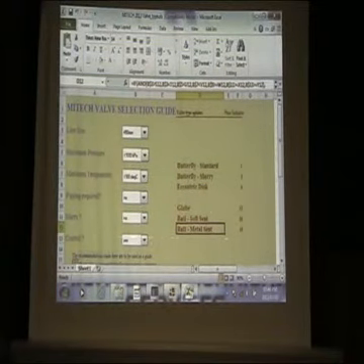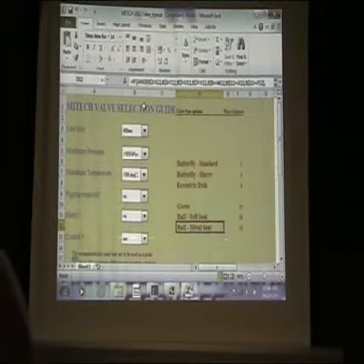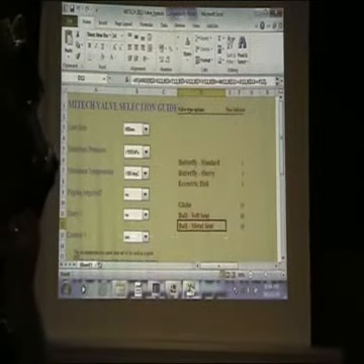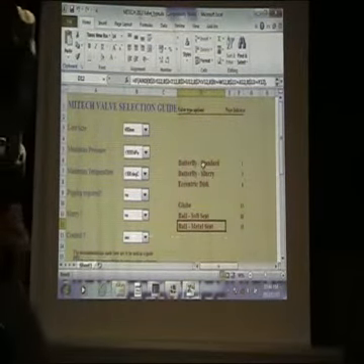Alright. So look at these options that you've got here. What are they saying? They say if you've got a 450 millimeter valve, and it's less than 1000 kPa. Remember 1000 kPa is 10 bar, eh? What did we say? You can use this thing on 10 bar. What is this program telling you now? What is your first option, the cheapest option? Go for the standard butterfly.